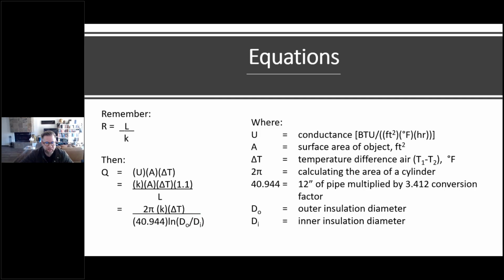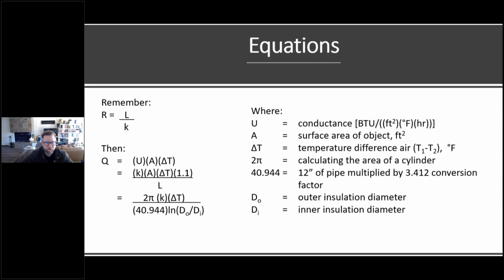Now, if you take those equations and you create charts, remember I told you that the ASPE heating manual only had one of the conditions. If you start creating charts for 1 inch thick insulation, 1.5 inch thick insulation, 2 inch thick insulation for various pipe sizes and various fluid temperatures, you're going to create a chart where you can see different BTU losses per lineal foot for the different fluids and temperatures. And as you notice, as you increase pipe size, your heat transfer rate increases. As you increase fluid temperature, your heat transfer rate increases. And again, we have some assumptions of a 0.24 BTU inch per hour foot squared degree Fahrenheit, basically for that insulation. And we're assuming a 65 degree Fahrenheit ambient air temperature. So again, some assumptions went into creating this, and this is kind of that next iteration that's in that ASPE Legionella design guide.